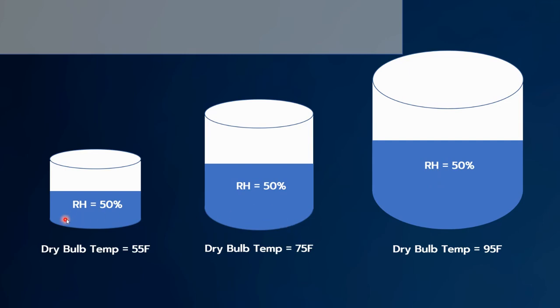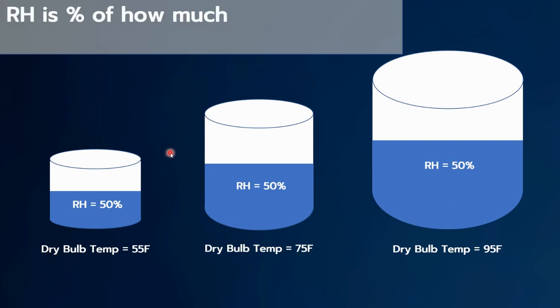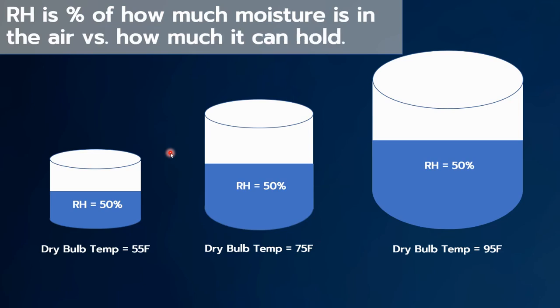They all have a relative humidity of 50% — they all have the same value — but look at the amount of moisture in each of these cylinders. It's greatly different. So what that tells us is RH is a percentage of how much moisture is in the air versus how much it can hold. It's not a good value to tell you the absolute amount of moisture in the air. Think of relative humidity as how full is the container.